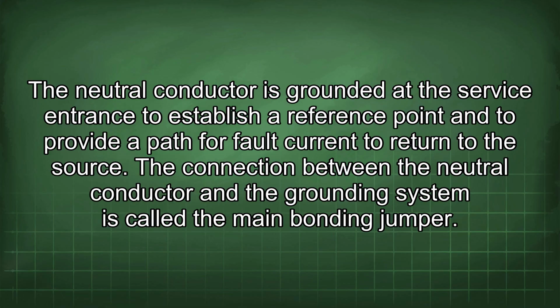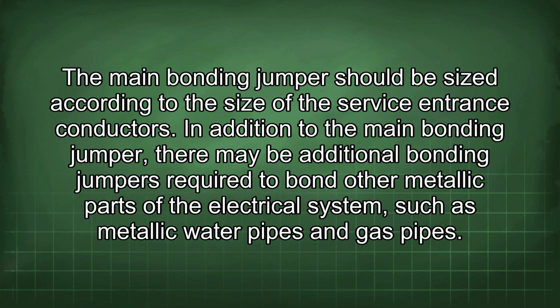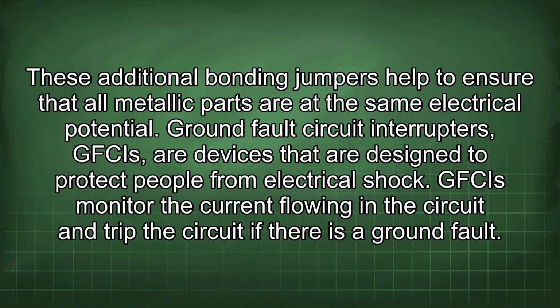The connection between the neutral conductor and the grounding system is called the main bonding jumper. The main bonding jumper should be sized according to the size of the service entrance conductors. In addition to the main bonding jumper, there may be additional bonding jumpers required to bond other metallic parts of the electrical system, such as metallic water pipes and gas pipes. These additional bonding jumpers help to ensure that all metallic parts are at the same electrical potential.